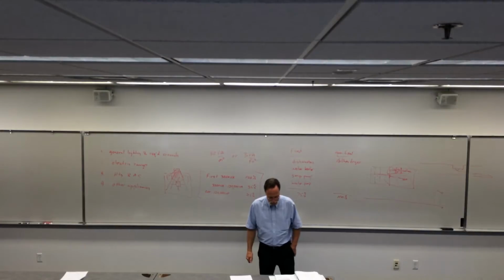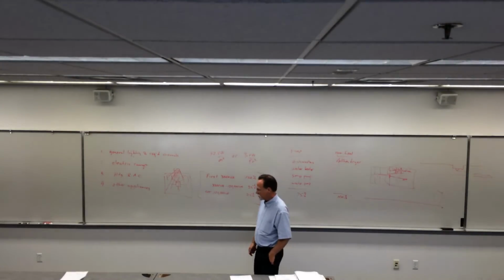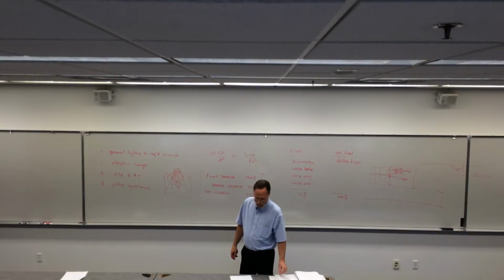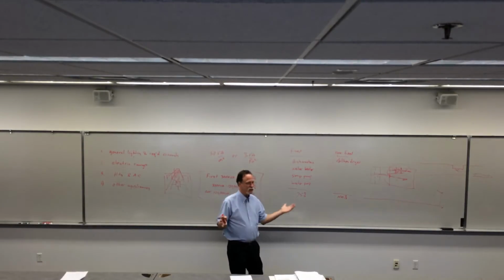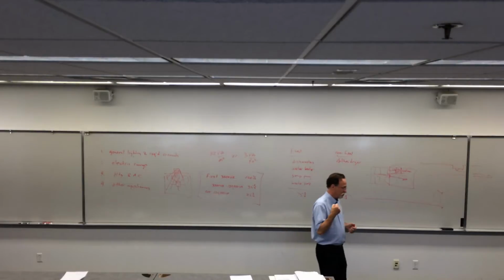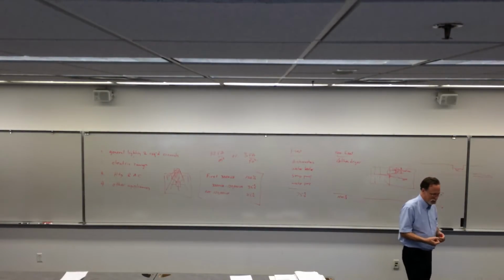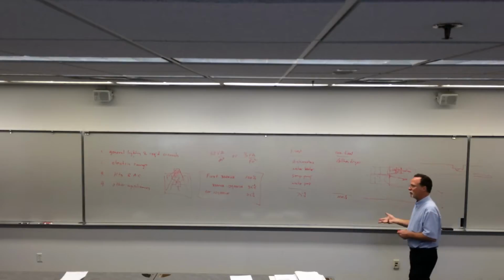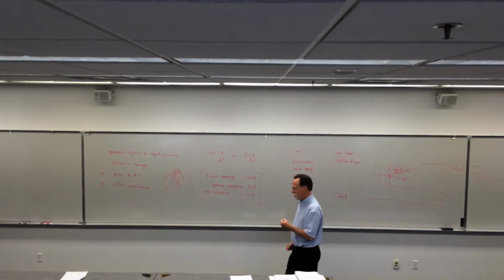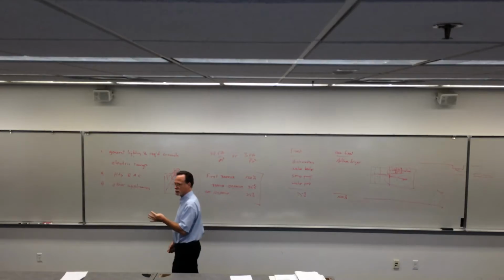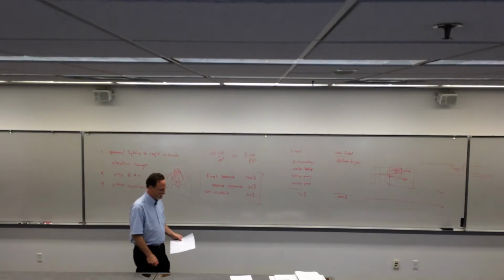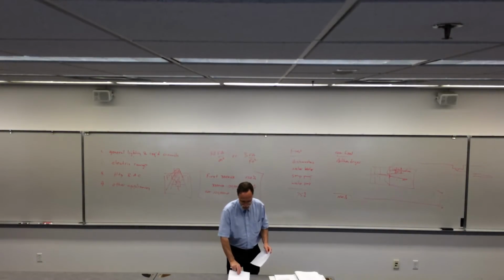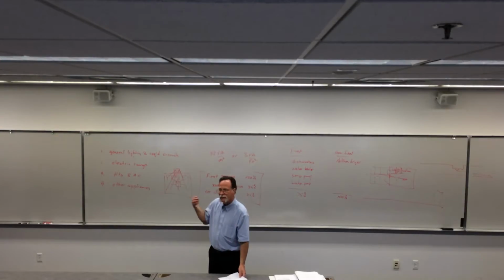So that's, in a nutshell, chapter 6. We've got the homework, which is problems 1 through 5, due on Friday. This was kind of an example of putting all of it together as separate problems on the range example, calculating the range, on the general lighting. Again, don't forget when they say required circuits, they're talking about bathrooms, laundry rooms, and 2 in the kitchen. If you have 2 bathrooms, you have to make sure that you count that second bathroom. And don't forget that required circuits, only an example where you have 1 bathroom.